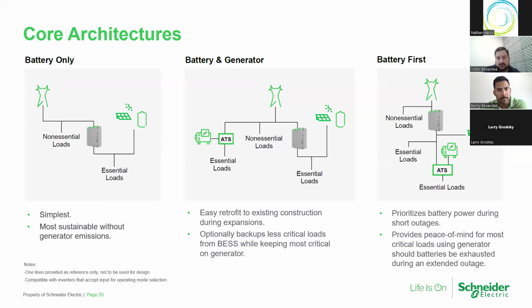And then on the far right, we have a battery first scenario. In the event that the battery energy storage system is upstream and you do lose power, instead of immediately sending a start signal to the generator to provide power to the essential loads, you run on a battery first scenario, where the battery energy storage system acts as the anchor or emergency anchor resource, providing power, basically inhibiting transfer so the ATS stays on normal.